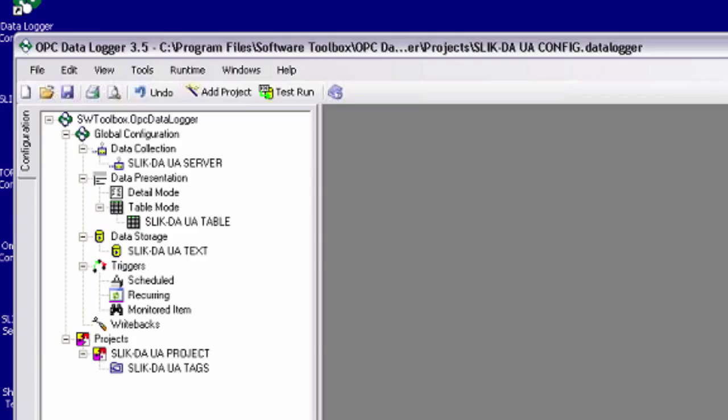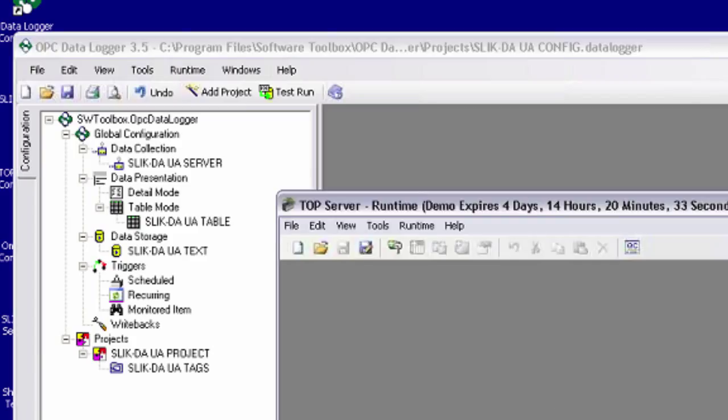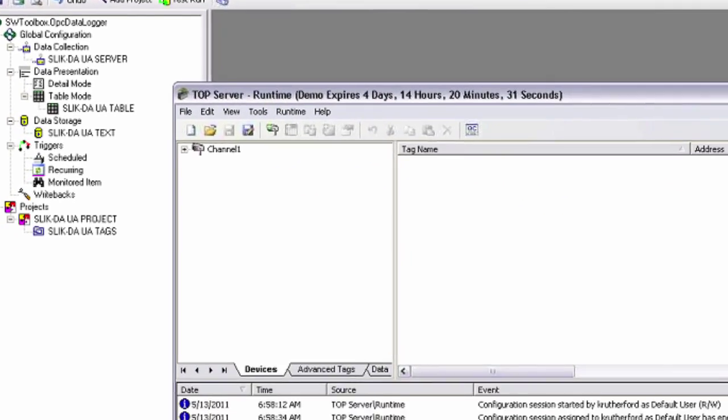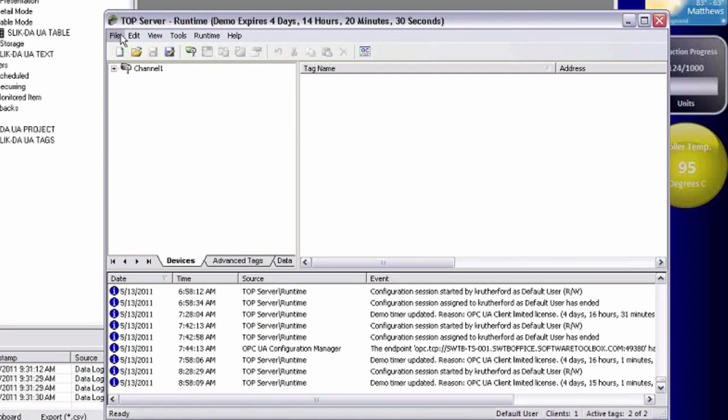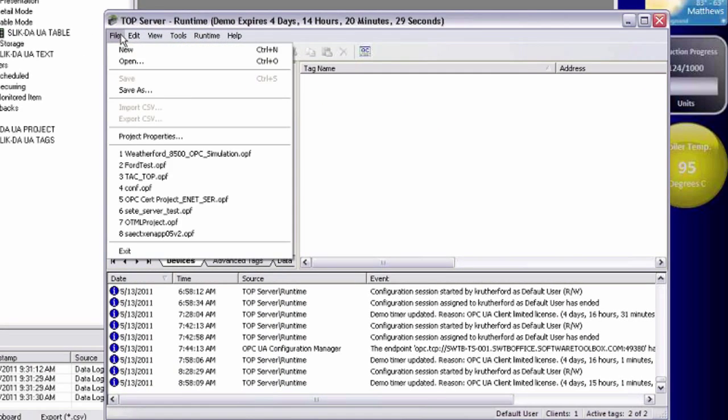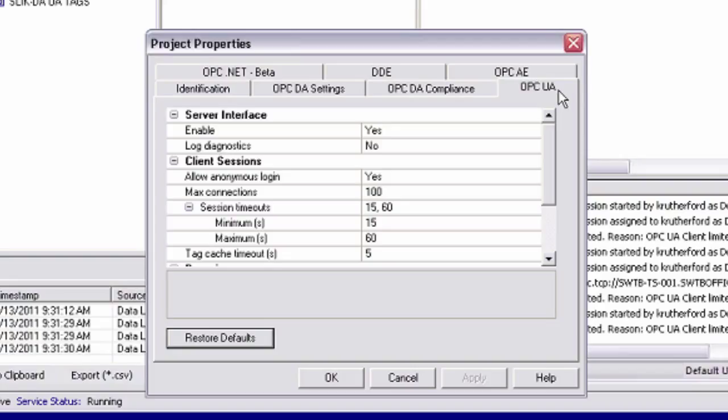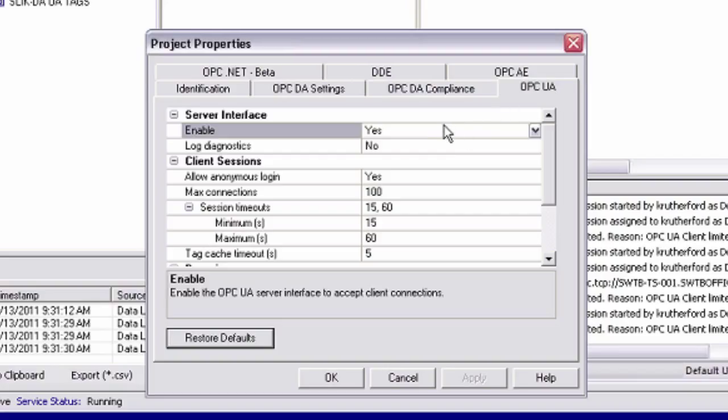Now for top server, I'm just going to go ahead and bring up my top server configuration and show you the steps that I went through to ensure that I'm able to connect to that. First, you go to file project properties, and we want the OPC UA section. Now the first thing for the connection is you want to make sure that the UA interface is actually enabled, that this is set to yes.